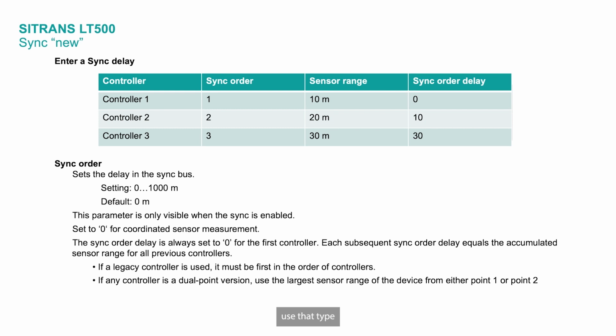If you are going to use that type of new sync functionality, there is a new parameter which becomes visible when you enable sync. What you need to do, if you're using two or more, is enter a sync delay. And we do that by entering what the sensor range is on your second application. So for your first controller or your primary controller, you don't need to enter any delay. On your second one, you just need to enter what the range is from the first controller.